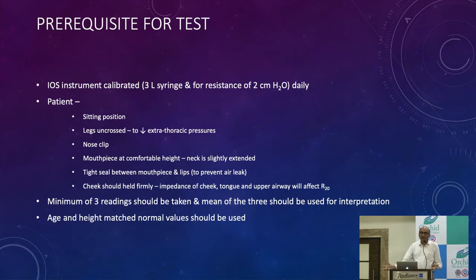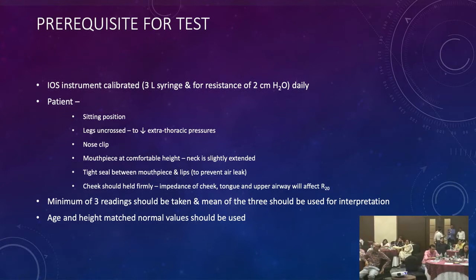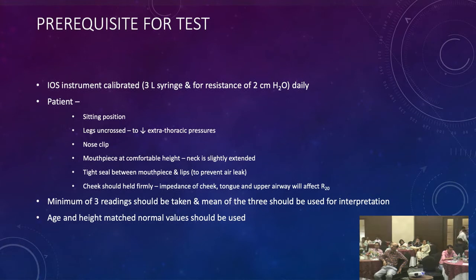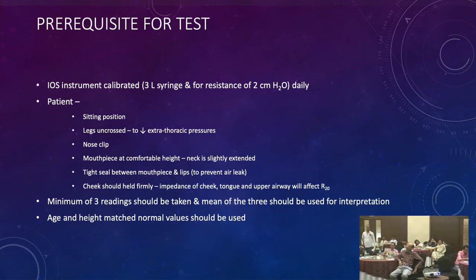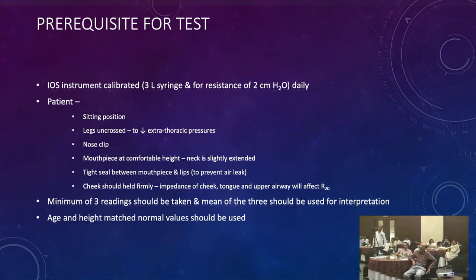Now, what are the prerequisites for the test? Very few. It has to be done in a sitting position, legs uncrossed, nose clip should be there so that all the flow occurs through the mouth, mouthpiece at a comfortable height, a tight seal between the mouthpiece and the lips, and the cheeks should be held firmly so that the sound waves do not dissipate in the cheeks.